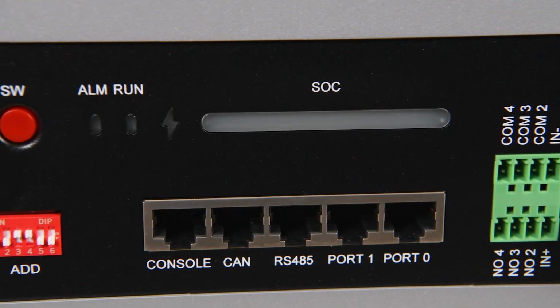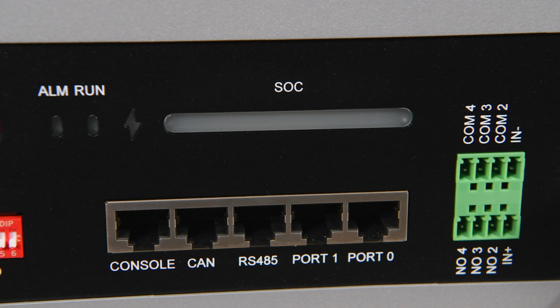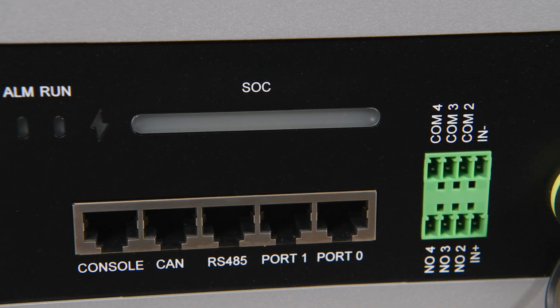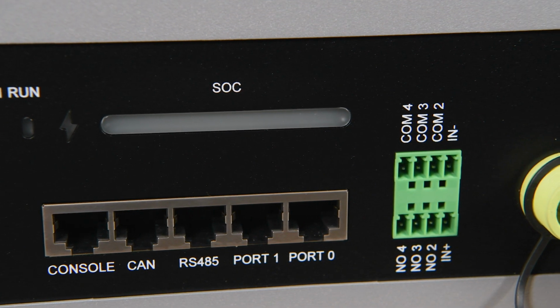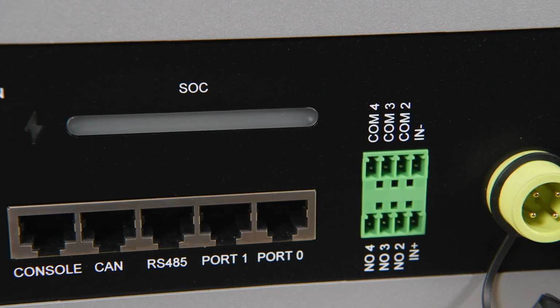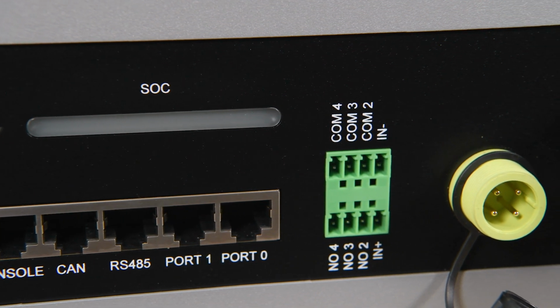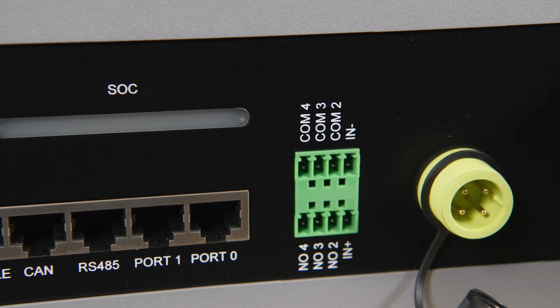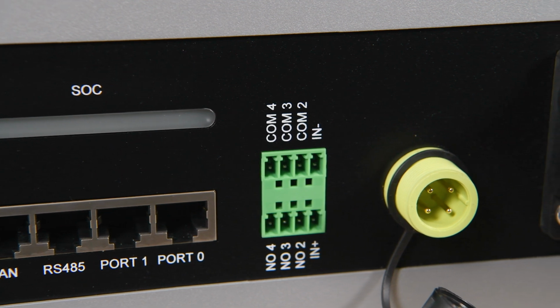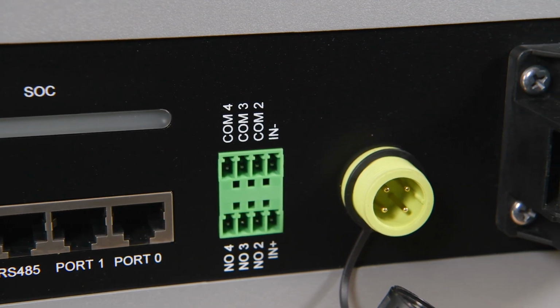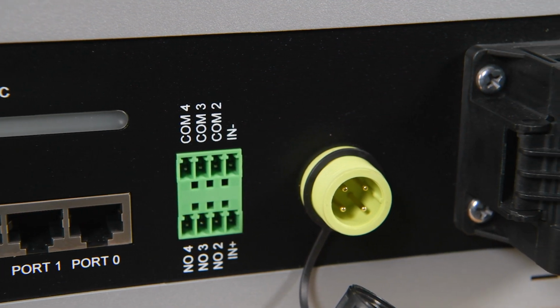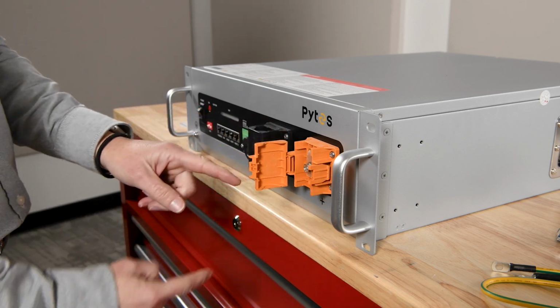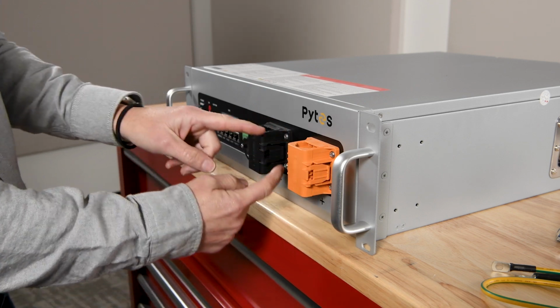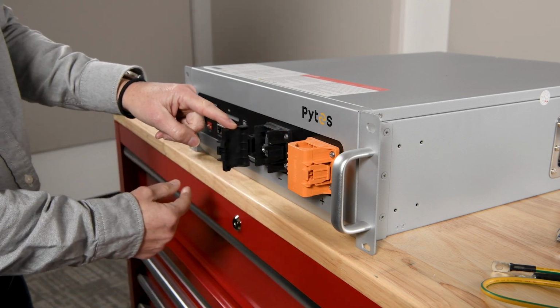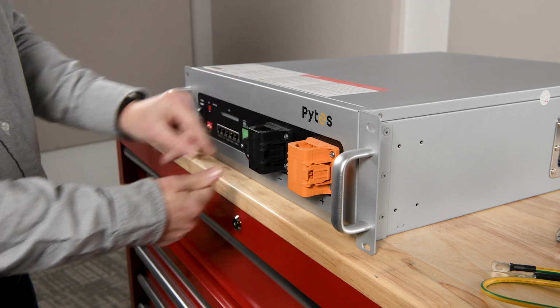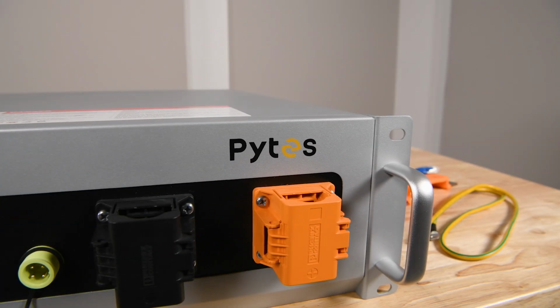Below that, we have the SOC indicator, which shows the battery's state of charge, and communication ports for CAN and RS-485 connections. For added versatility, there's a dry contact port and an IoT port, enabling remote firmware updates and data collection for diagnostics, again through the SolarMan platform. Lastly, you'll see the negative and positive power terminals, each with easy access push-button doors and top and bottom knockouts to accommodate your battery cables.